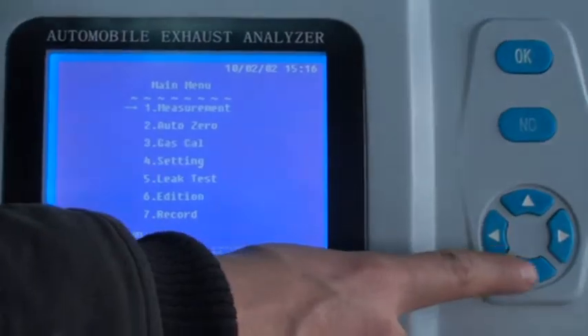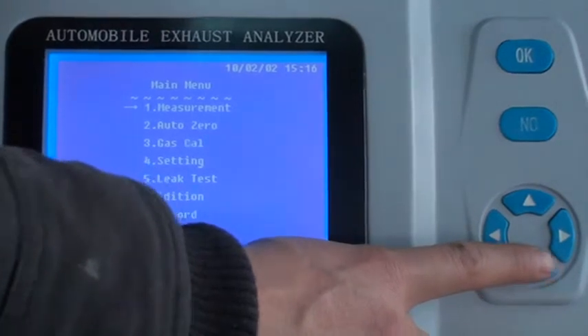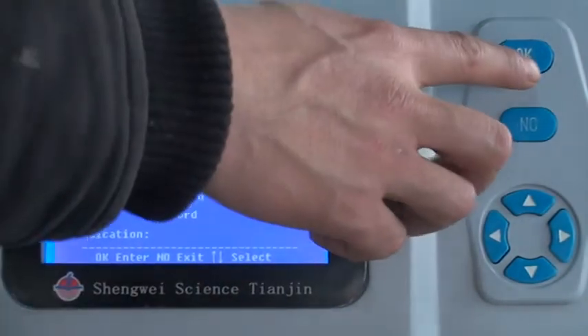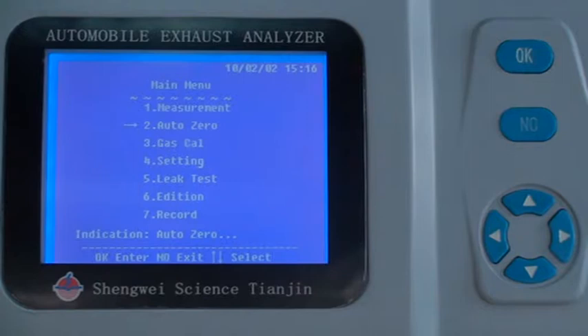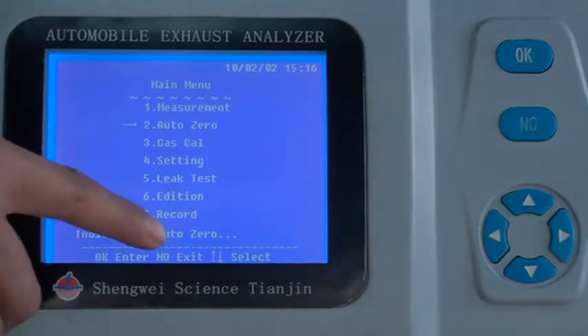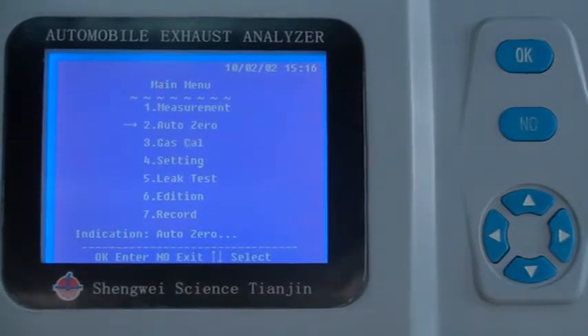If in the measurement it shows zero drift, exit and enter the main menu. Choose the second item, auto zero calibration. Auto zero maybe needs 1 minute to make sure there is no zero drift. When the operation is finished, there will be a notice at the bottom of the LCD.